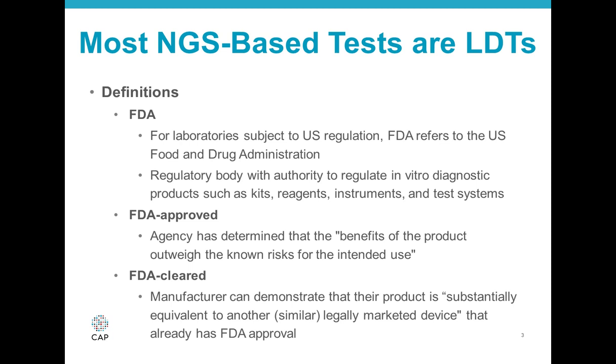So now for just some basic definitions. What is the FDA? For laboratories that are subject to U.S. regulation, the FDA refers to the U.S. Food and Drug Administration regulatory body that has the authority to regulate in vitro diagnostic products such as testing kits, reagents, instruments, and testing systems. FDA-approved basically means that the agency has determined that the benefits of the product outweigh the known risks for the intended use of the product.